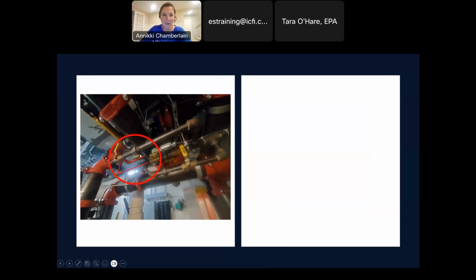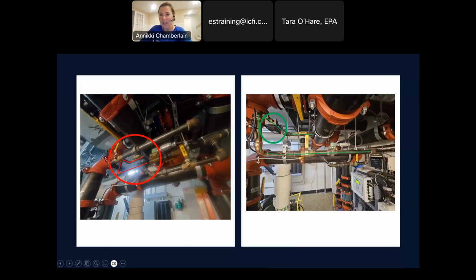Here's another one I thought was very clever. It's kind of hard to see, but this is the main condenser line. So the line comes off, and again, I didn't have enough straight pipe by the time it came through this blowdown valve. So this one, they changed it, came off. So here's my meter right here. And so you can modify it pretty easily. So if you don't have the straight pipe, typically you can find it. If you are on a drain after the valve, same thing, you just have to put in basically a U-trap. And so even if the pipe isn't under pressure, that trap will always be full, and I've done that a lot.